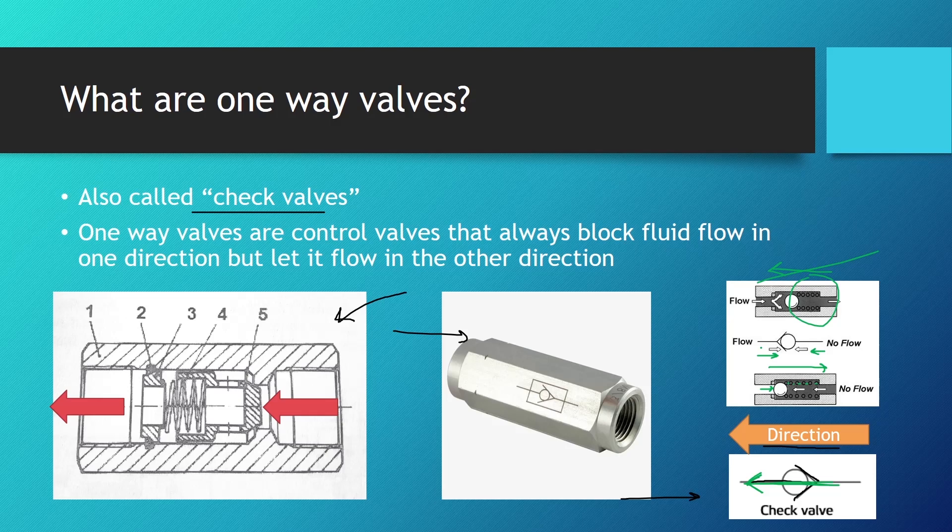One-way valves are used for preventing backflow. They are used as low pressure relief or filter bypasses. They are used when we have to hold loads with minimal leakage, and they are used for switching and sequencing. We will see one example at the end of the lesson.